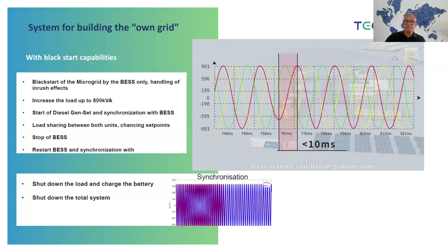You see here on the right side the three phases. If they have some frequency problems, the three phases are shifting. And if the shifting is not stopping within 50 milliseconds, then you have a blackout. In this time, the storage system has to bring the capacity into the grid with a reaction time of 10 milliseconds. You have to use, in this case, a good inverter system and also a grid-forming inverter system.